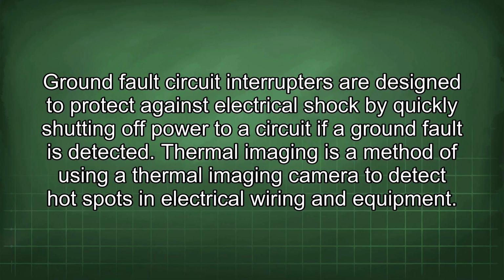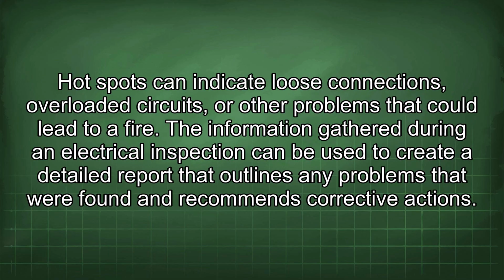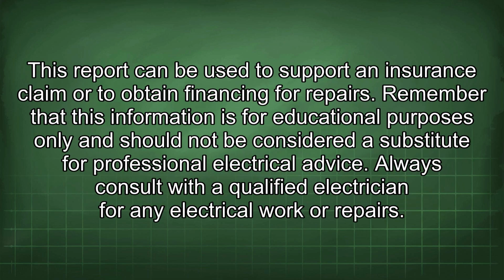Thermal imaging is a method of using a thermal imaging camera to detect hotspots in electrical wiring and equipment. Hotspots can indicate loose connections, overloaded circuits, or other problems that could lead to a fire. The information gathered during an electrical inspection can be used to create a detailed report that outlines any problems that were found and recommends corrective actions. This report can be used to support an insurance claim or to obtain financing for repairs.